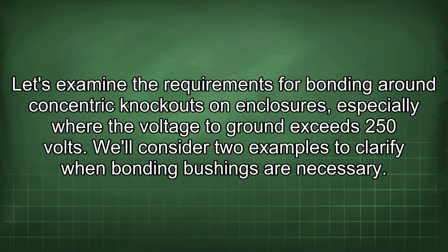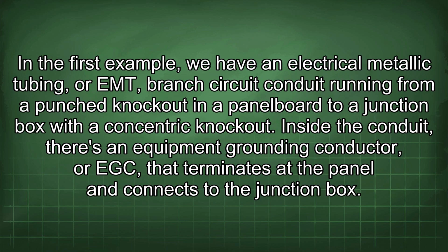Let's examine the requirements for bonding around concentric knockouts on enclosures, especially where the voltage to ground exceeds 250 volts. We'll consider two examples to clarify when bonding bushings are necessary. In the first example, we have an electrical metallic tubing or EMT branch circuit conduit running from a punched knockout in a panel board to a junction box with a concentric knockout.